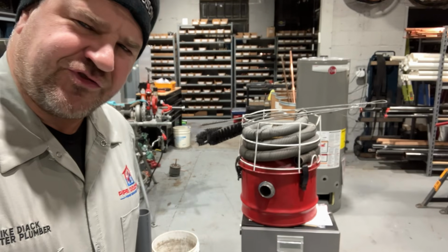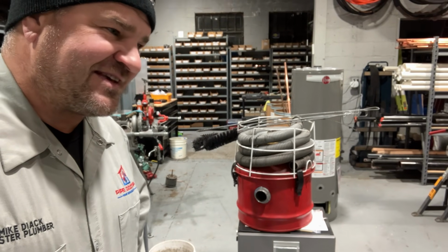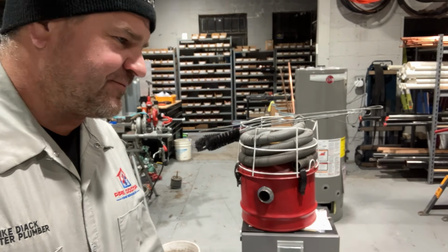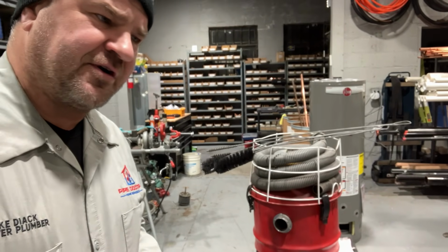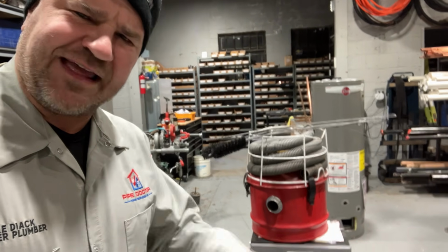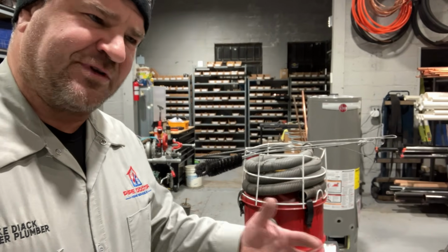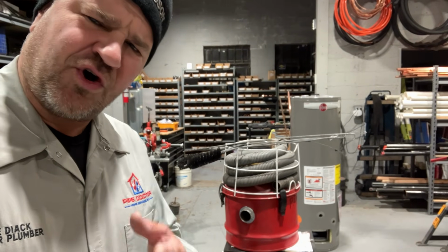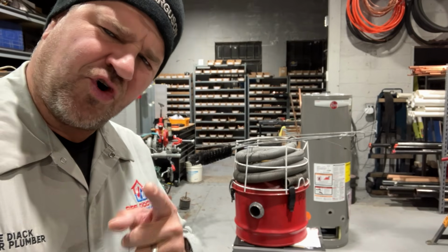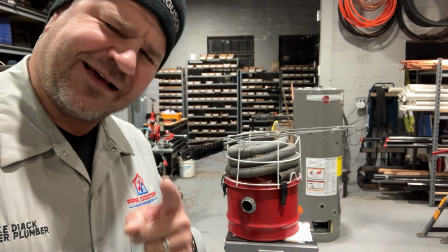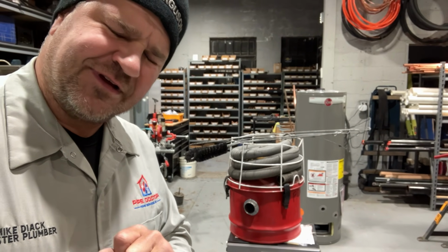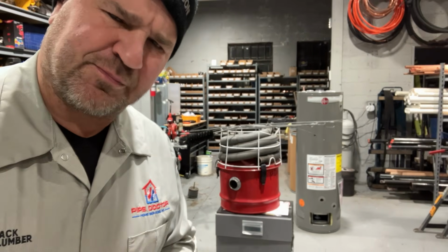I'm about to go on this job that we probably see about 6 or 7 times a year. I got a fully carbonized boiler. It's all sooted up. We got flame rollout. The rollout switches have been tripped. And the best part is it all could have been prevented if the homeowner called a qualified and licensed HVAC professional instead of trying to change the pilot burner on his own.